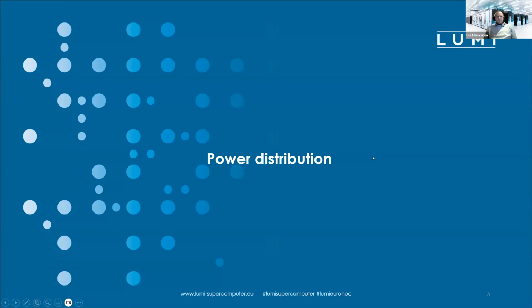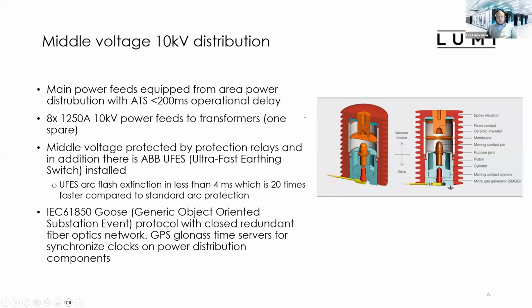So then the power distribution of the Lumi data center. We have this medium voltage 10 kilovolt power distribution from the area's transformers. And our main power feeds are equipped with an automatic transfer switch, which has less than 200 milliseconds operational delay. So basically, if our primary power feed for the data center is lost, it takes less than 200 milliseconds to automatically switch the power feed from primary to secondary. We have in place 8 1250 amp 10 kilovolt power feeds to our transformers, and one of those is spare, so 7 transformers are installed in our data center facilities.